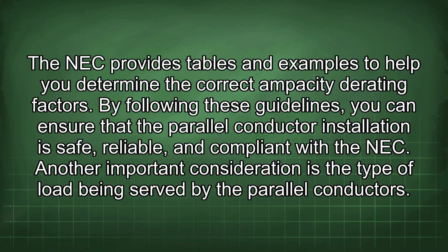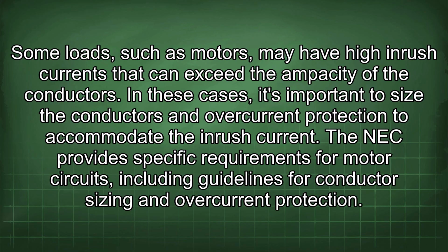Another important consideration is the type of load being served by the parallel conductors. Some loads, such as motors, may have high inrush currents that can exceed the ampacity of the conductors. In these cases, it's important to size the conductors and overcurrent protection to accommodate the inrush current. The NEC provides specific requirements for motor circuits, including guidelines for conductor sizing and overcurrent protection.